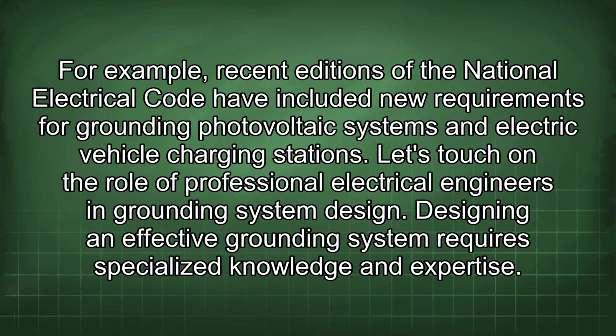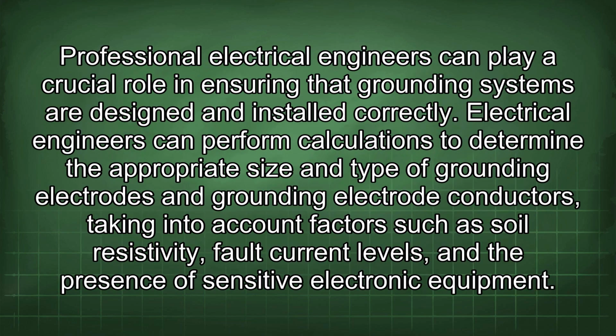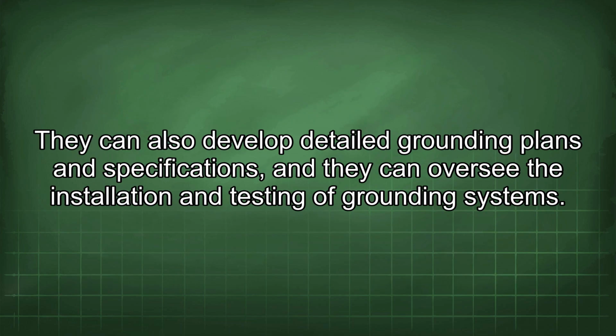Designing an effective grounding system requires specialized knowledge and expertise. Professional electrical engineers can play a crucial role in ensuring that grounding systems are designed and installed correctly. Electrical engineers can perform calculations to determine the appropriate size and type of grounding electrodes and grounding electrode conductors, taking into account factors such as soil resistivity, fault current levels, and the presence of sensitive electronic equipment. They can also develop detailed grounding plans and specifications, and they can oversee the installation and testing of grounding systems.